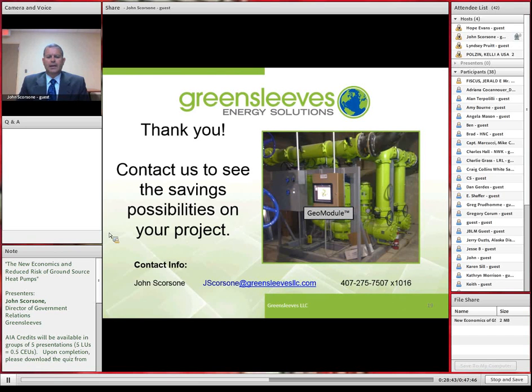No, we don't. And I will say that in general, while we can integrate with that and understand how it's behaving and adjust our system to account for its actual performance, we're not a very big advocate of the horizontal loop. The main reason is because horizontal is so close to the surface of the earth, it's more reactionary than the deeper earth vertical bores, but certainly less reactionary than outside air systems. In home applications, they're pretty popular, especially up in the Northeast, so we can integrate with that. I don't think we have any current projects where we have.